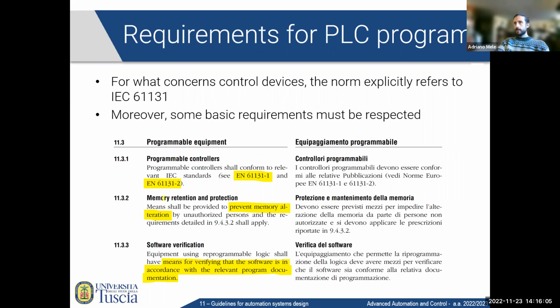Second, there is another safety issue. You see that means should be provided to prevent memory alteration by unauthorized persons, and requirements detailed in this paragraph shall apply. For example, if you remember, we told that PLCs usually have a key switch. They have a physical switch from programming mode to operating mode. And if you have a key, then some unauthorized personnel could not go there and just plug in a USB key or some Ethernet cable and change the programs inside the PLC, because you need to physically switch it on the programming mode.